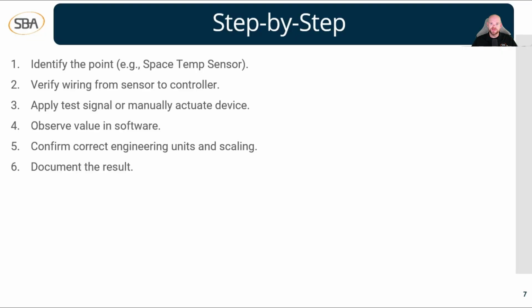And then the final thing here is to document the result of this test. So we just tested one point, which is a space temperature sensor. And once we've done all this, if we got good proper readings, if our software has been configured correctly, we go to our documentation template that we already pre-created, and we'll document in there the result. Yes, it was good, no problems, or it was not good. Here's what we found. This is what we're going to do to fix it. That's typically how the step-by-step process works for this point-to-point checkout.